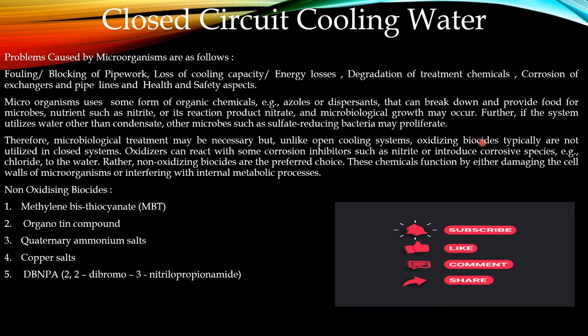Microbiological treatment may be necessary in CCW systems. Unlike open cooling water systems, oxidizing biocides such as chlorine, chlorine dioxide, ozone, and hydrogen peroxide typically cannot be used in closed cooling water circuits, because these active oxidizers can react with corrosion inhibitors like nitrites or introduce corrosive species such as chloride into the water. Non-oxidizing biocides are therefore the preferred choice; these function by damaging the cell walls of microorganisms or interfering with internal metabolic processes. Non-oxidizing biocides used in CCW systems include methylene bisthiocyanate (MBT), isothiazolinones, quaternary ammonium salts, copper salts, and DBNPA (dibromonitropropionamide).